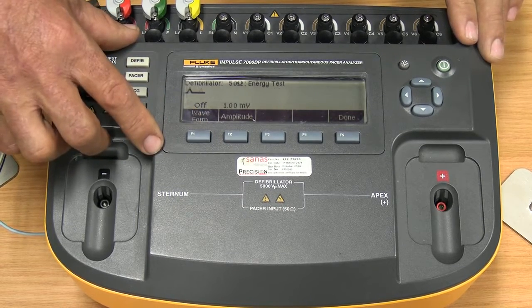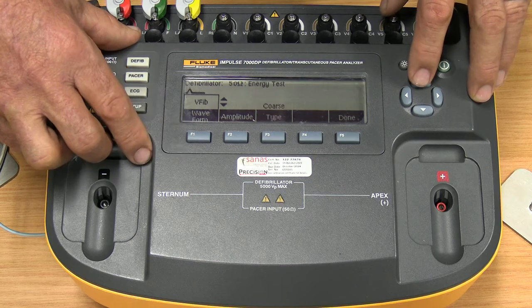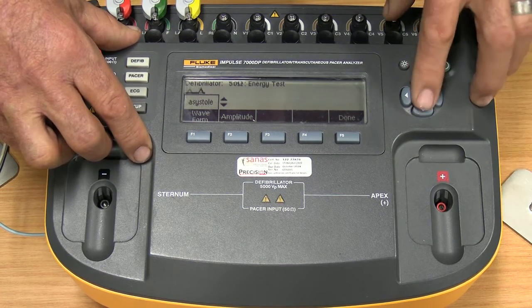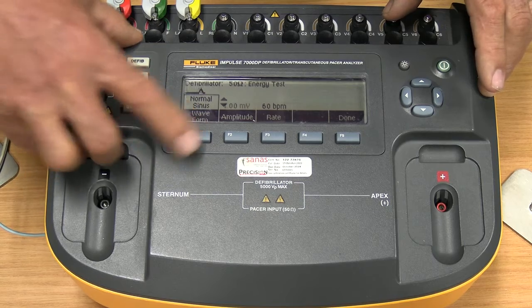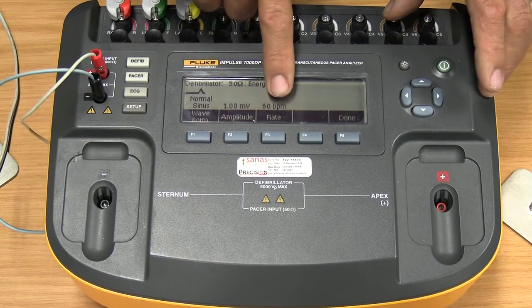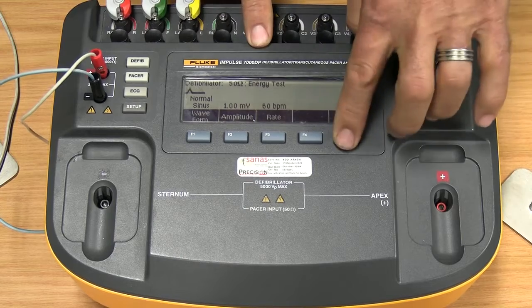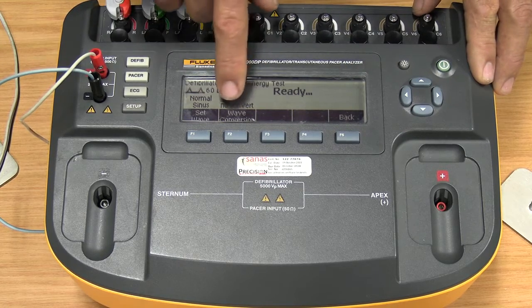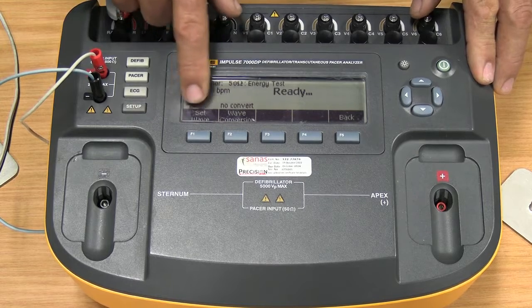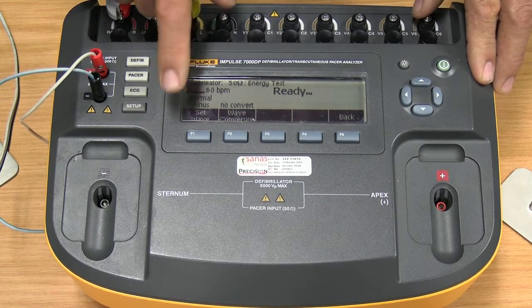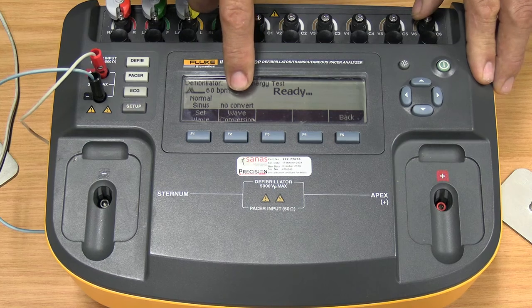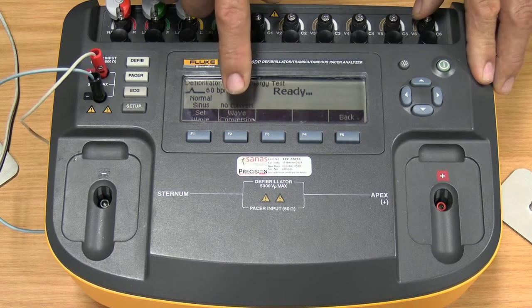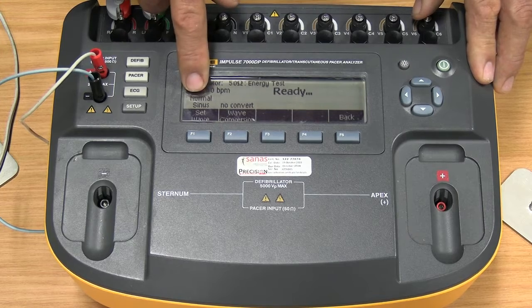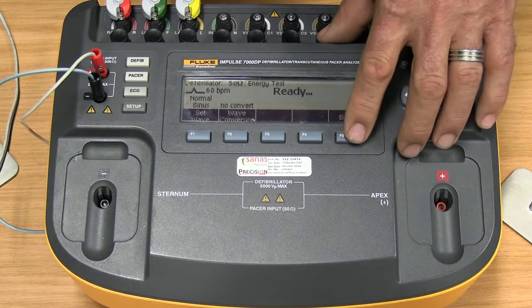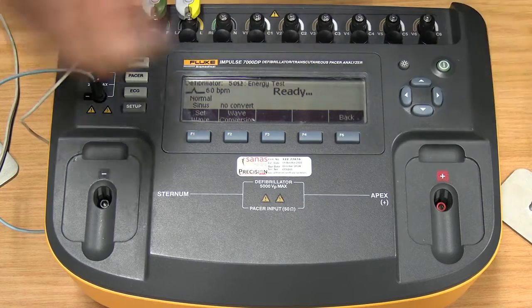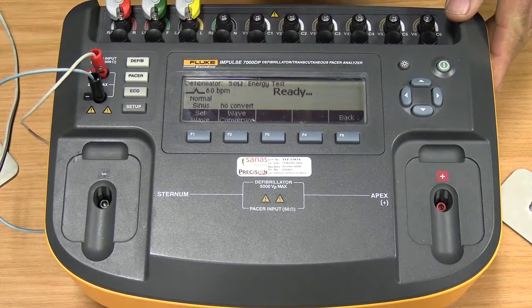If I want an ECG wave, I can press the function, and with the up and down arrows, I can choose whichever waveform I would like. Once you've chosen, then the amplitude and the rate is available for change as well. If we say done, you see it stays there. Wave conversion, meaning that if I've set a fibrillation, for instance, a VFib, after the shock, it will then change to a normal waveform if I've put it on convert. If I say no convert, it means it will stay on the set pulse, the waveform. And once the machine says ready, you can apply your paddles and you can shock, and you will get your energy delivered.